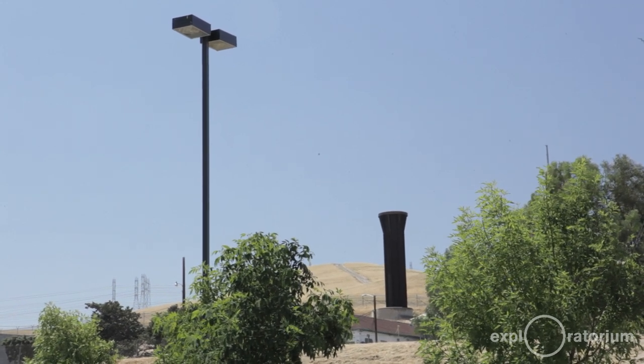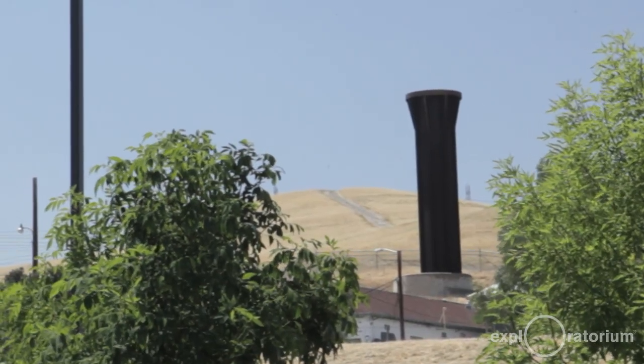One of the more distinctive features of the landscape here is a 50-foot black tower visible from 10 miles away in any direction, behind me over my right shoulder — that's the entrance to our tunnel, which is 26 miles long going to the Bay Area. That tower is essentially a big surge chamber: an empty tower going up 50 feet. If pressure changes on the demand side of the whole water system — customers taking more or less water — the water has a place to go, rising and falling in the shaft. It gives the system an ability to relieve pressure instead of blowing up a pipe, which is what the Romans learned 2,000 years ago when they shut a valve and their terracotta pipe blew apart for miles upstream.